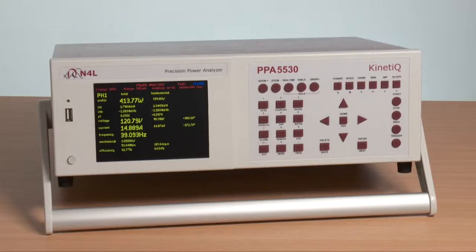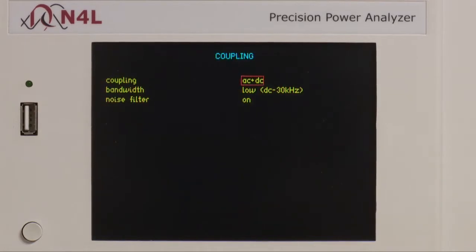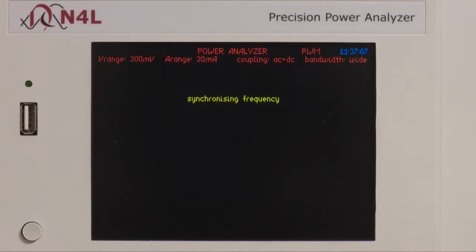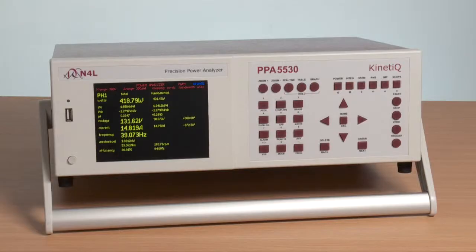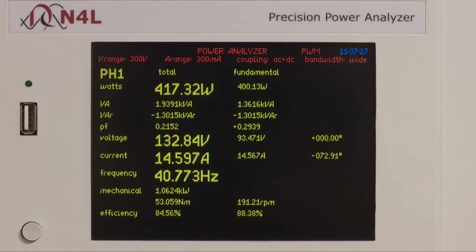Here you can see that while we are still in low bandwidth, we have a nominal 120 volts phase to neutral. If we now reselect wide bandwidth, giving DC to 2 MHz, the voltage is increased to 131 volts. So we have approximately 10 volts difference due only to frequency components above 30 kHz. Since switching frequency components are present in both the voltage and current signals, it is clear that filtering will reduce the accuracy of wideband measurements.